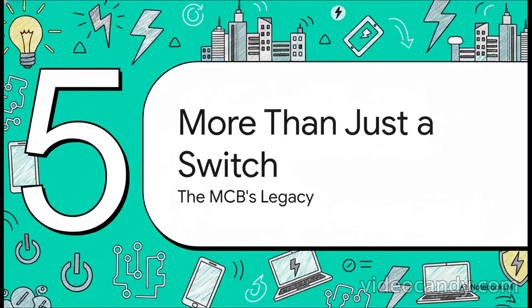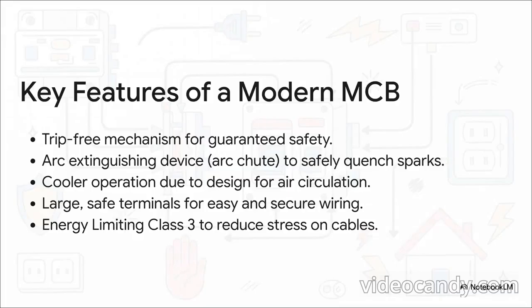Why? Well, think about a big motor. When it starts up, it draws a huge but very brief surge of power. A sensitive Type B would trip every single time. The Type C is designed to ignore that initial kick and not cause a bunch of annoying false alarms. So as we wrap up, it's pretty obvious the MCB is way more than just a switch. It's a really sophisticated piece of protective tech that honestly enables our entire modern way of life.